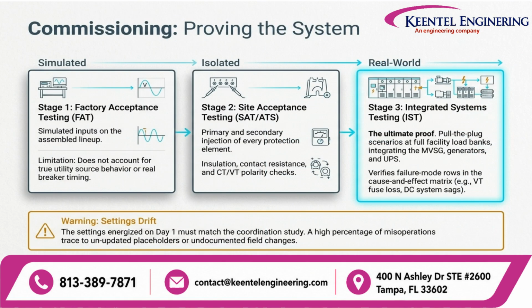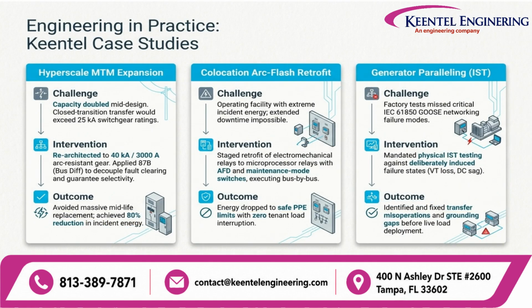outages. Commissioning is the ultimate proof of a system. From factory and site acceptance testing to final integrated systems testing, each stage is vital. Always ensure that the final settings in the field match your original coordination study. Real-world case studies demonstrate the importance of these engineering practices.